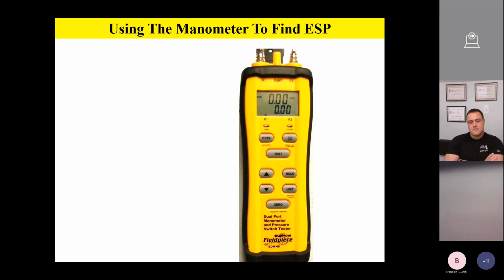You can also use what we call a magnehelic gauge, which is a large round gauge that reads in inches of water column. And if you're really old school, you can go back to the inclined water manometer, which is basically about 18 inches long, filled with water, and it sets on its side. That's kind of old school, but most everyone nowadays uses a digital manometer. So we're going to be featuring this digital manometer today as the featured tool.